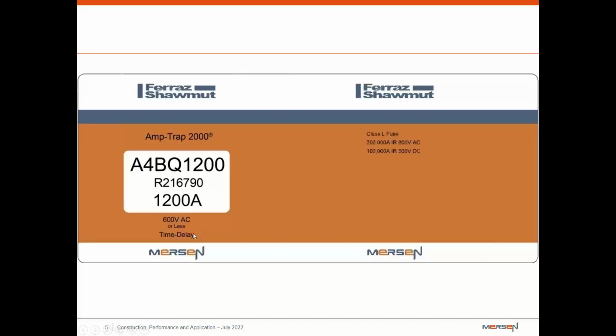First things first, let's start off with as basic as I could get and how to read a label. So this is going to be an A4BQ. You can see the name of the fuse right there. It's going to be a 1200 amp fuse. Just underneath that is going to be a reference number. That's for us so that we know what fuses have been tested to what specifications and to make sure that they actually meet those. And under that, you're going to have the ampacity. So this is going to be a 1200 amp fuse.